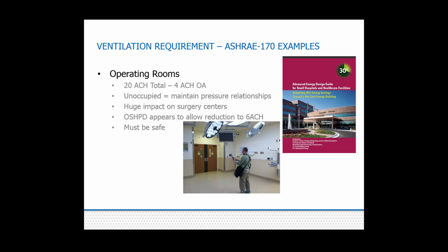So for an operating room, the requirement is for 20 total air changes when occupied. In unoccupied, the only requirement is to maintain the pressure relationship, which, depending on how airtight your operating room is, may take a couple hundred CFM, could take as much as 1,000 based on some anecdotal things we've heard from people who have done blower door testing in operating rooms.